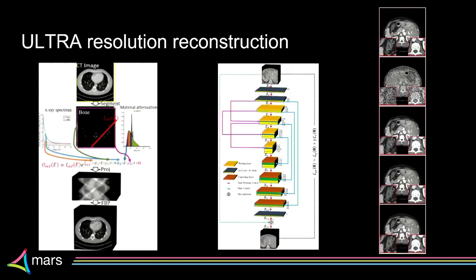We can also do things like ultra-scale resolution. Advanced model-based reconstruction can take a huge amount of computation power, which is actually a good thing for machine learning — we can train models based on the result of spending massive amounts of computation. If we then supersample from a lower-computation solution to that higher resolution, we can essentially do this in real time. Rather than waiting weeks for your CT to be reconstructed, we've trained a model to go from a cheap reconstruction — using typical back projection with a lot of extra physics integrated in a modified U-Net — to produce a very high-resolution result, even though you spent very little computation time generating it.